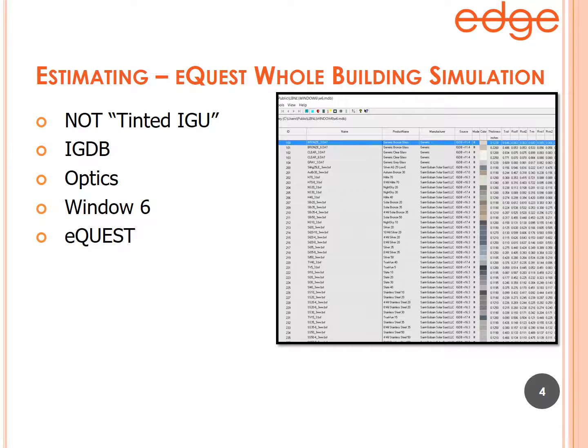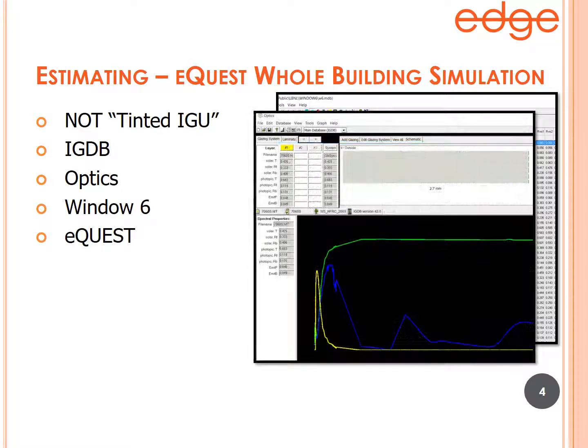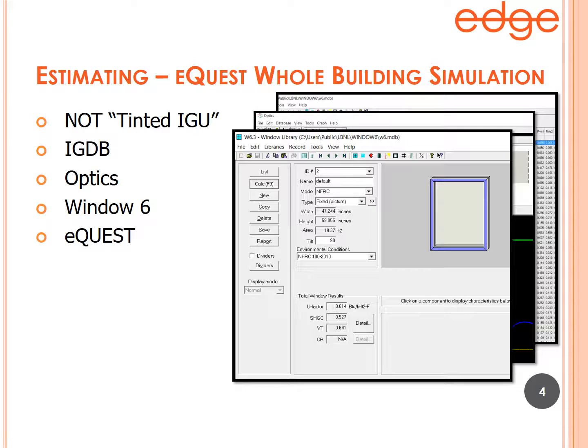When the glass type isn't available in the database, you go to a software created by Lawrence Berkeley Labs called Optics. Inside Optics, you can take any real glass and any real film and use this software to combine them and get the performance of that actual film on actual glass. You can then take the result into another Lawrence Berkeley Lab software called Window.